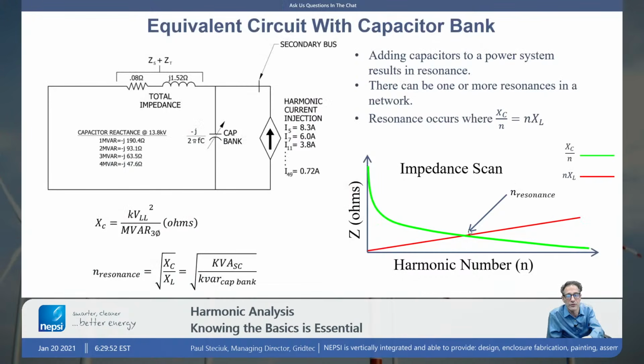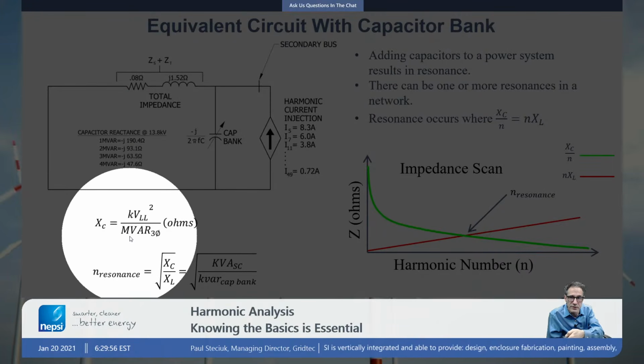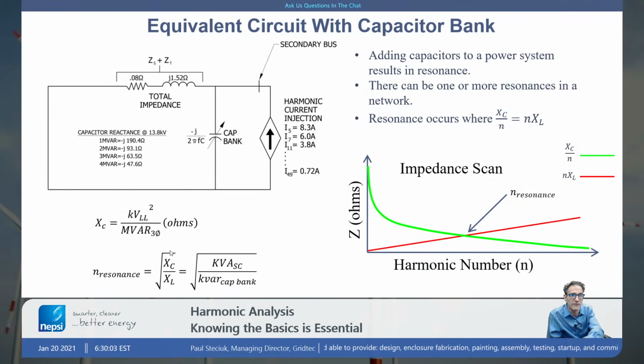There's a crossover point. That crossover point we refer to as resonance. For a very simple circuit like this, you can calculate that resonant number. It's equal to the square root of X of C divided by X of L. So you take the fundamental value of X of C, the fundamental value of X of L, divide those numbers, take the square root, and you have the harmonic resonant number, what harmonic it's resonating at. What's important to note here is that this formula only works for this system configuration.